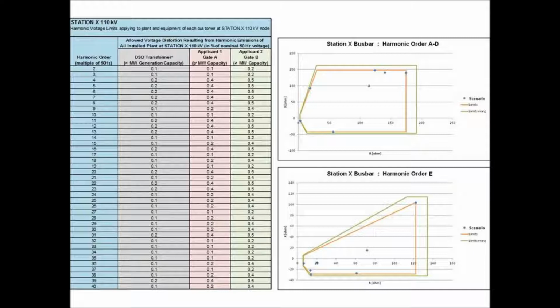So that's basically it. Each of those blue dots, I hope everybody can see them, corresponds to a scenario. So it might be intact case, it might be N-1, it might be winter night, or winter peak, or summer night valley, or whatever it happens to be, or future expansion. And then you draw these squares all the way around it. So there's a set criteria for how to draw the squares. You can pick the furthest most to the right and draw a straight line straight down. The top one and the bottom one you draw a horizontal line straight across. And then you start off at the origin and just start spanning out until you hit one, and whatever the angle is there, you'll use that as your first angle up and angle down. So as long then as you can remain within these squares, you'll be compliant with the grid code, providing that your harmonic injections, your current injections don't get larger than what's allowed. So that's the plan anyway, to stick to below those limits and within those impedance loci.